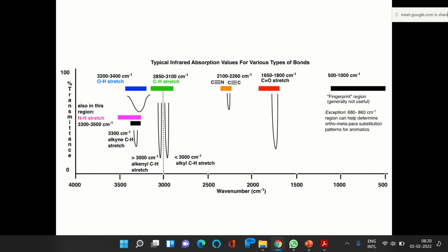Going into far IR requires change of the optical window, so that again becomes slightly difficult. So usually what we do is the KBr pellet method. KBr is transparent in that mid IR region, so it is widely available and useful. The other method, which is now getting more popular, is the ATR accessory. The FTIR that we have installed in our lab has both options.